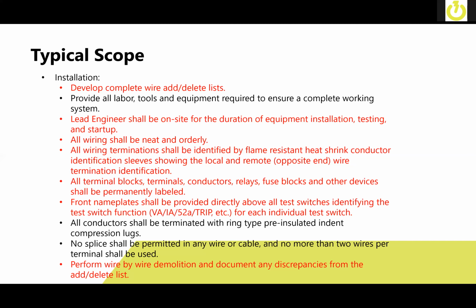Splices, as I mentioned, you typically would like to take the new wire that's going in and completely pull it back to its termination point versus trying to splice it in the middle. A lot of times if you put more than 2 wires per terminal, it ends up making the screw not be able to turn down tight enough, and you end up having connection problems and inconsistent operation.